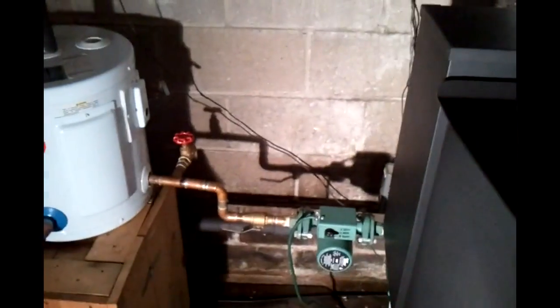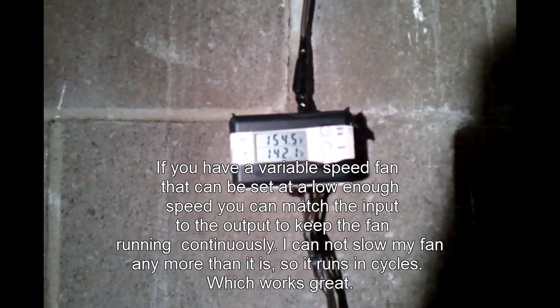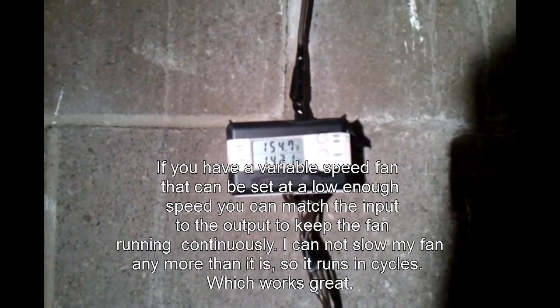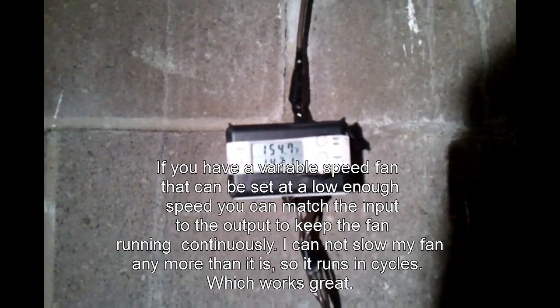Now there's an aquastat on the water line here that's hooked to the furnace fan, and what that does is when the water temperature coming in is 160 degrees, it'll turn the furnace fan on, and when it drops down to 140, it'll shut the furnace fan off. It'll take about 5 minutes to bring it back up to 160, and then the furnace fan will run another 4.5 minutes, and that'll just cycle like that to where I'll get 5 or 6 cycles an hour.